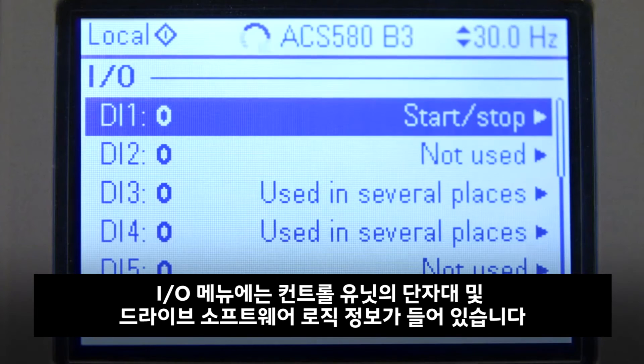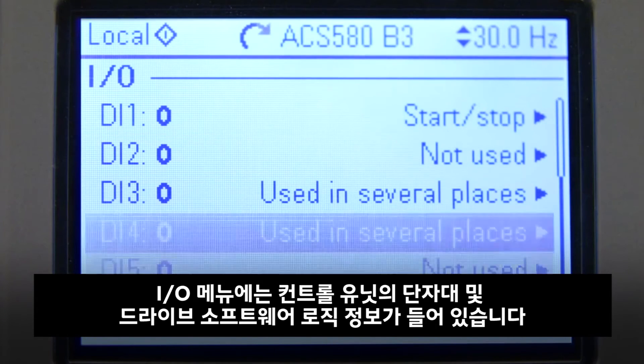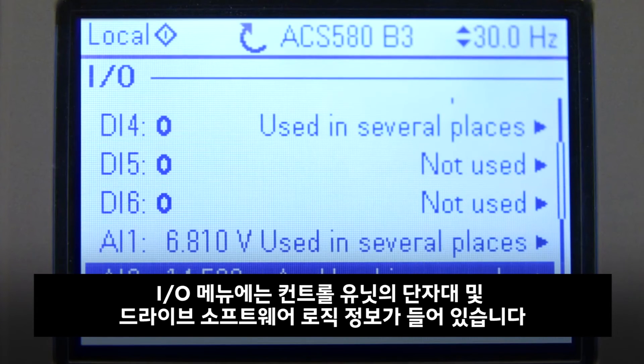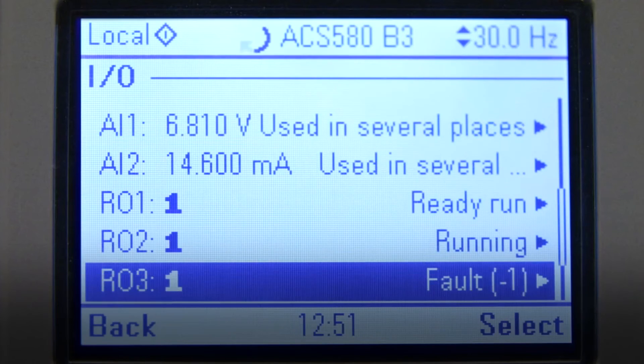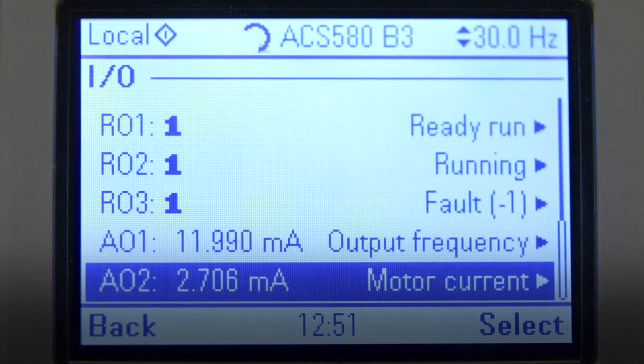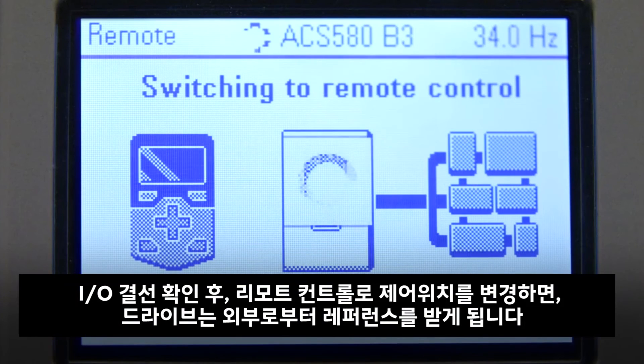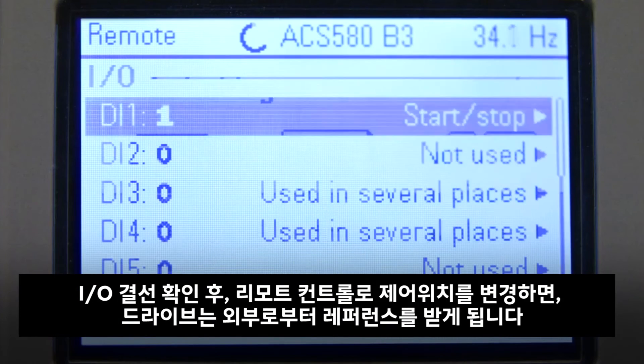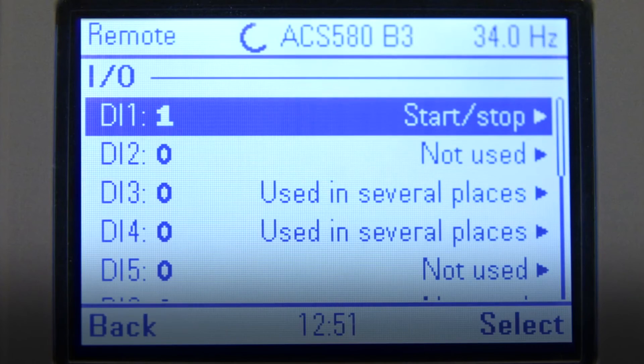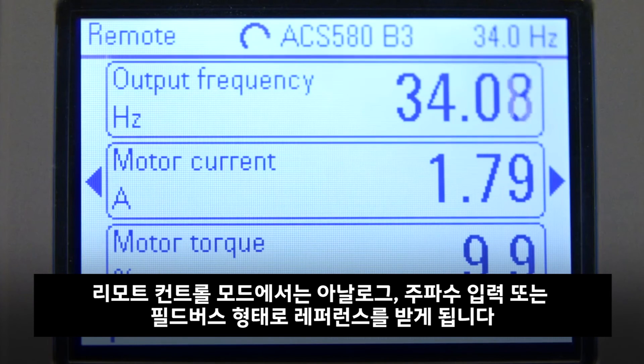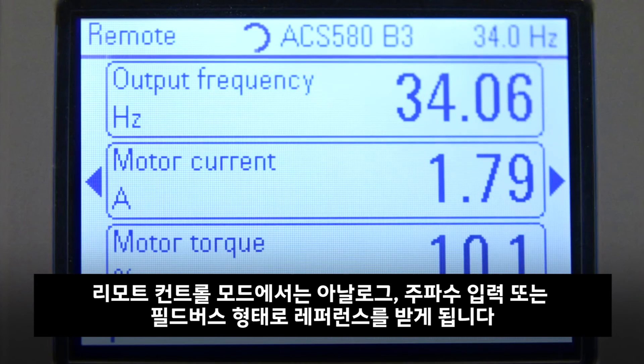The I/O menu holds information on the control unit's terminals and their logic in the drive software. After checking the I/O connections, the control location is changed and the drive gets the reference from the remote location. Remote control location gives reference through analog input, frequency input, or via fieldbus.